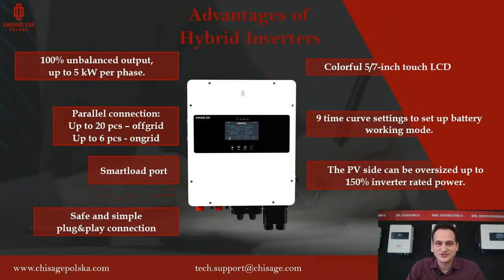So what about the advantages of our hybrid inverters? First of all, the 100% unbalanced output. We can have maximum 5 kilowatt per phase for all inverters. So no matter the power, we have 5 kilowatt per phase unbalanced output. We can connect up to 20 pieces in parallel for off-grid mode, and 6 pieces in on-grid. We support a smart load, so we can connect any load. We add some conditions for when we want to supply this load or not, and the inverter will manage this.